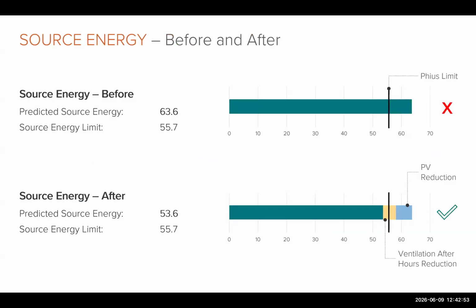However, it turned out that even with those allowances, we still couldn't quite meet the target. We had to dig a little bit deeper into our toolbox. The first thing that we did was add that PV that you saw on the roof. We added as much as we could, and that brought our source energy down the amount shown in blue there. So we came down from around maybe 64 to 58. It was closer, but not quite there.